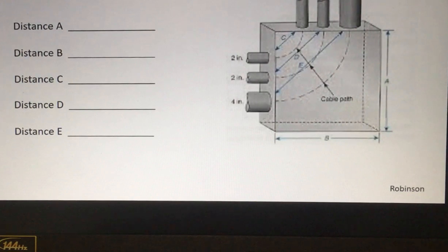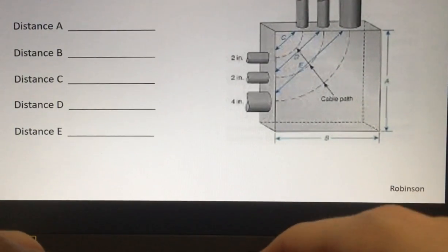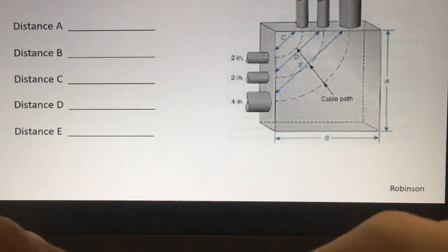See if you can solve that for an angle pull. The answers are in the book, Professor. Oh no, never mind. You're wrong. 28 by 28. All right, how do you figure that? Well, 4 times 6 is 24, plus 2 plus 2. Okay, 28. And the other side is the same.